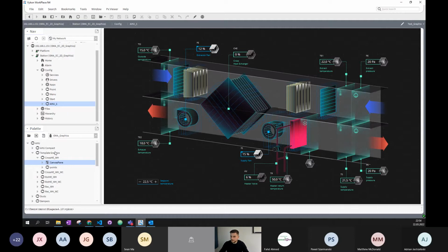So air handling units, it's really simple. I would also like to show you the FCUs because FCU is a little different. There is a slight difference because in the FCUs we have a template for the whole device, whether it's BACnet or Modbus. You have 4 types of FCUs that you can implement.